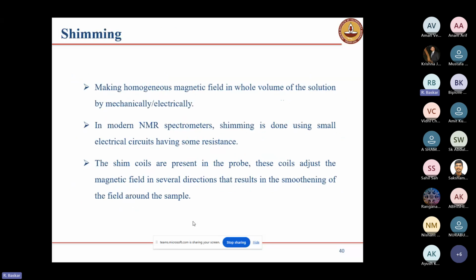Next, once locking is done, the next step is shimming. Shimming is making a homogeneous magnetic field in the whole volume of your solution. Because when you prepare the solution and take it in an NMR tube, compared to the top portion, the bottom portion has more molecules. The outer magnetic field we have already locked. The bottom portion of the NMR tube has more molecules than the top portion. The outer magnetic field is constant, but the effective magnetic field of individual nuclei is varying.